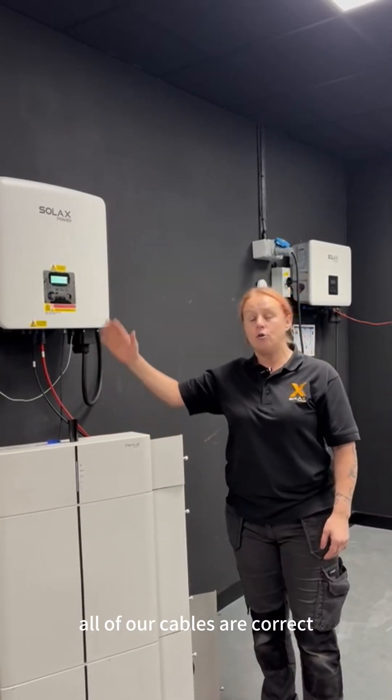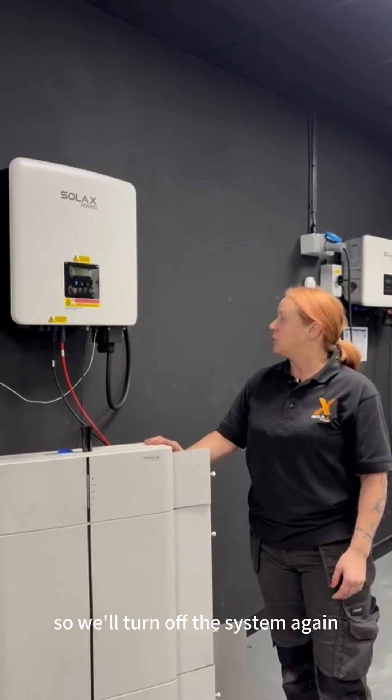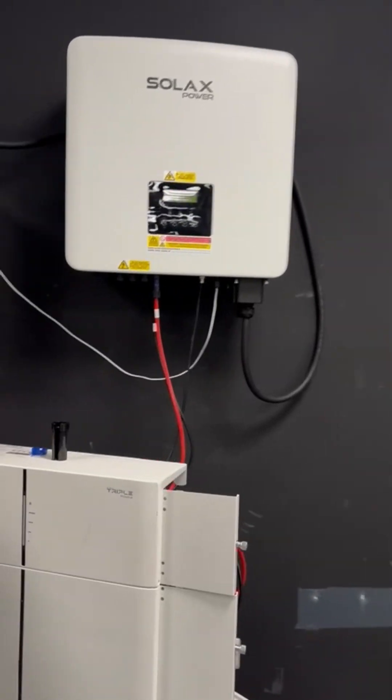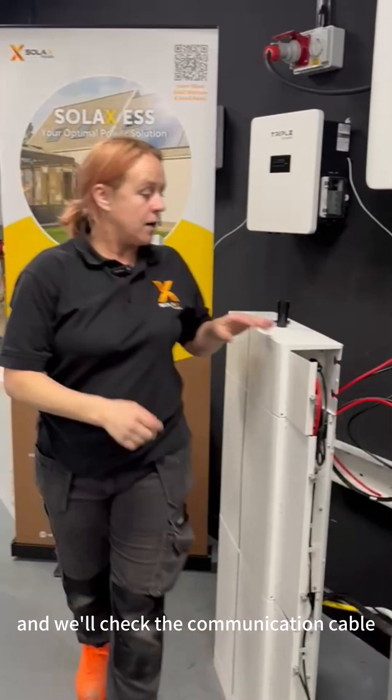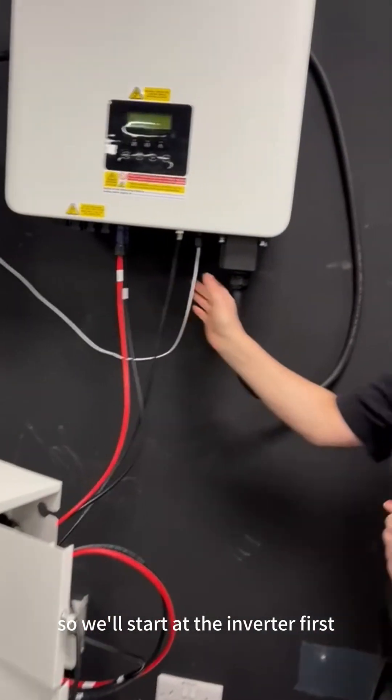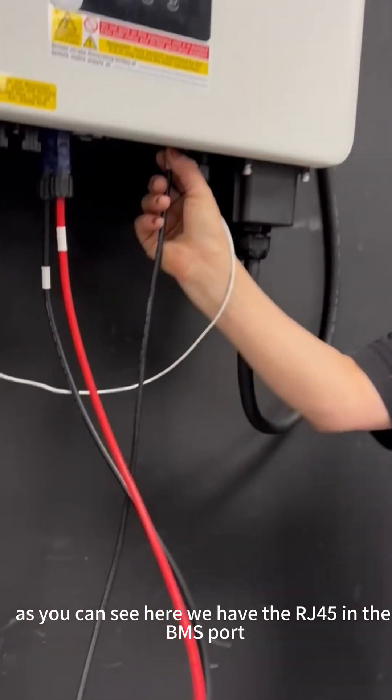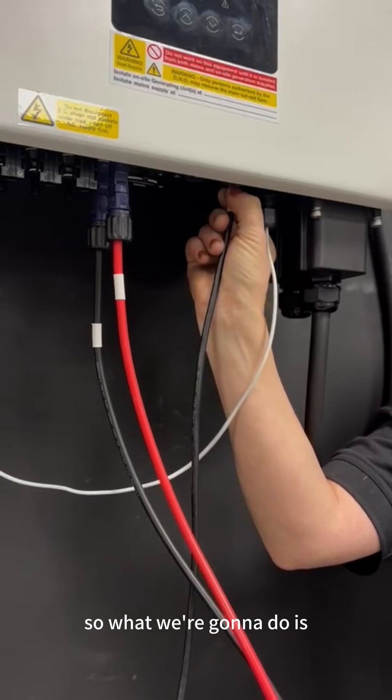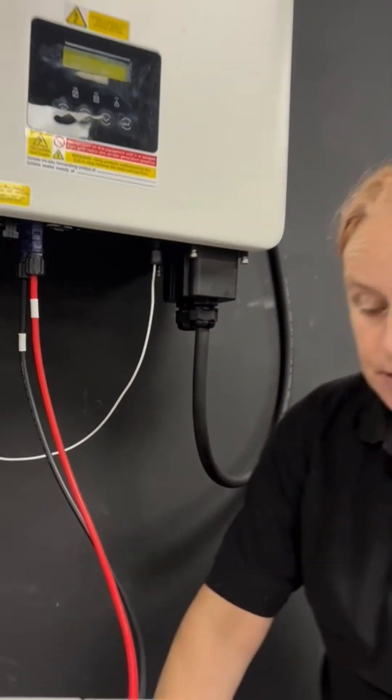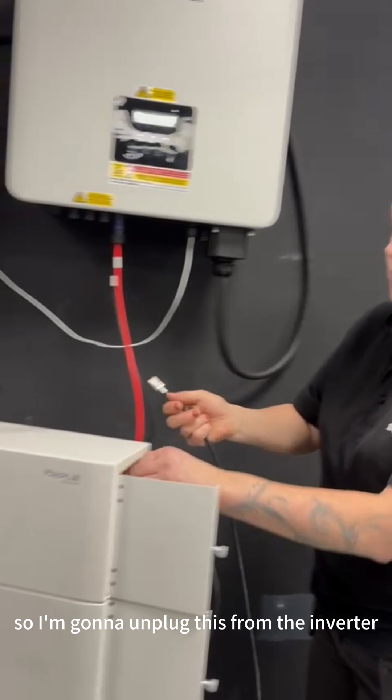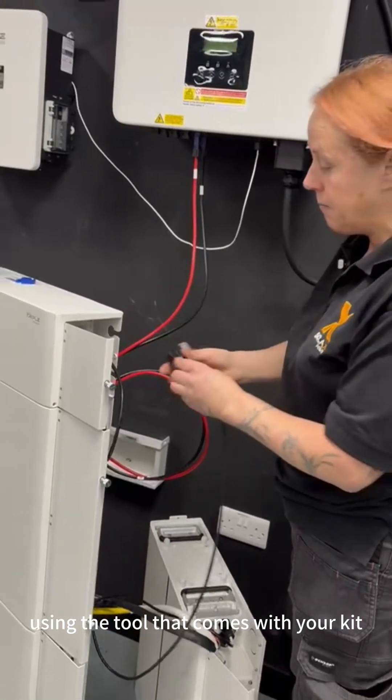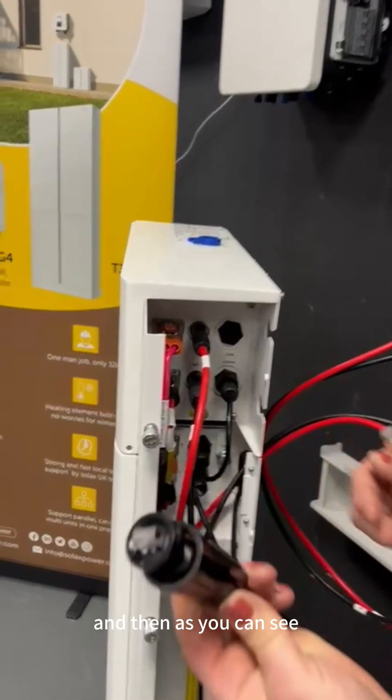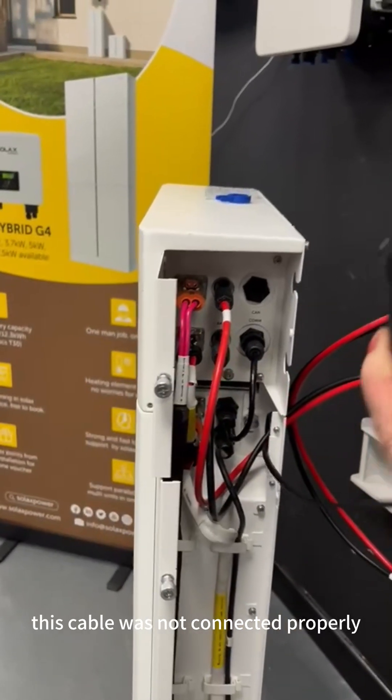In normal mode, these lights will be flashing green every five seconds. So because we're not working, we now need to verify that all of our cables are connected correctly. So we'll turn off the system again and check the communication cables. We'll start at the inverter first. As you can see here, we have the RJ45 in the BMS port. However, we do not have the IP cap on.